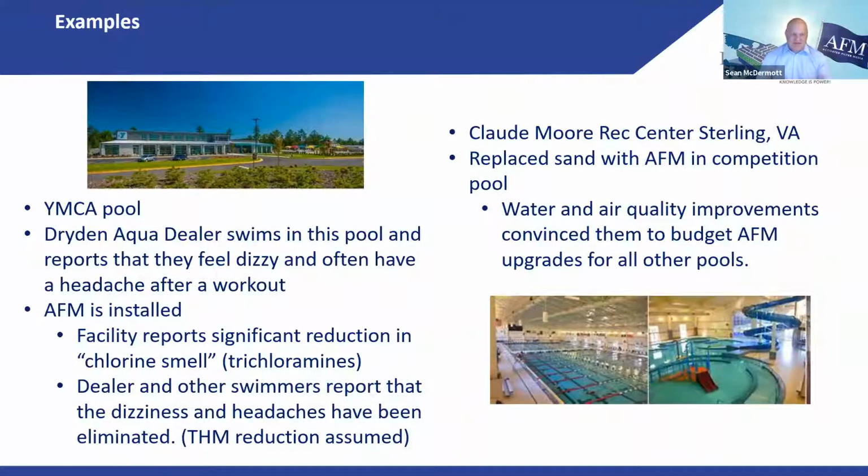We recommended AFM, of course. They're a dealer. They were able to have the YMCA install AFM. The facility immediately reported a significant reduction in the chlorine smell, or the trichloramines in the air, and that was immediate. And then the dealer followed up with us and said, I don't have the dizziness and the headaches anymore, and people that I swim with are reporting the same thing. So we would assume in this instance a reduction of THMs, of chloroform as well. So that's an excellent case study, an excellent example of reduction of trichloramine and trihalomethanes.